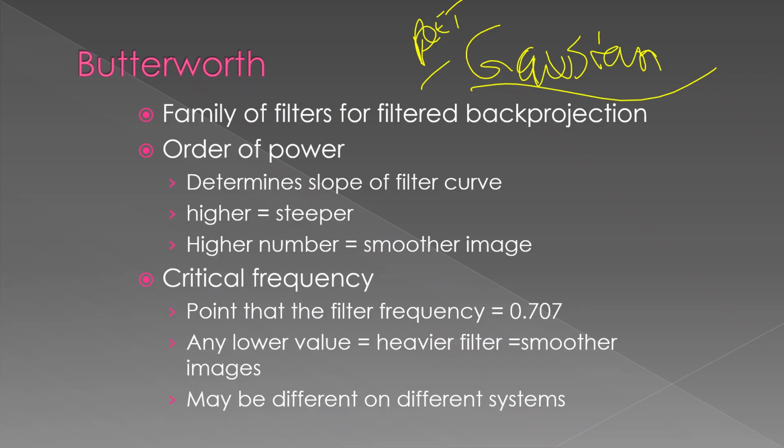But Butterworth is a family of filters for filter back projection. This used to be used in older PET systems, and it's still mostly used in SPECT. If you have a really older PET system, especially if it's standalone, you may see that it's using a Butterworth filter, but it has an order and a critical frequency, whereas most other ones just have one critical frequency that it uses as its cutoff.